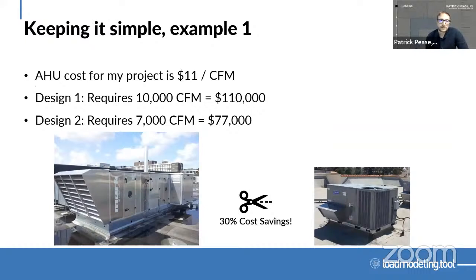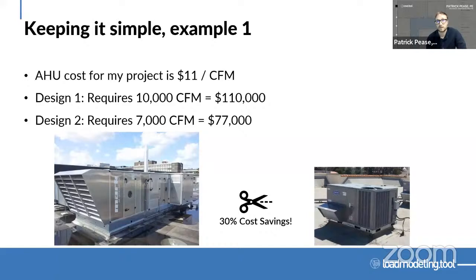For example, perhaps air handling units for a project cost $11 per CFM all-in for a package system. If one design requires 10,000 CFM based on internal loads and glazing, that's about $110,000. Now if I have an alternative design where I've reduced plug loads, gone with slightly higher performing glass, and reduced the peak CFM needed to cool the space to 7,000 CFM, I get a 30% cost savings on that unit alone. Even before the formal cost estimate, I can do these quick calculations as I'm designing to see if I'm making a positive impact and optimizing costs.